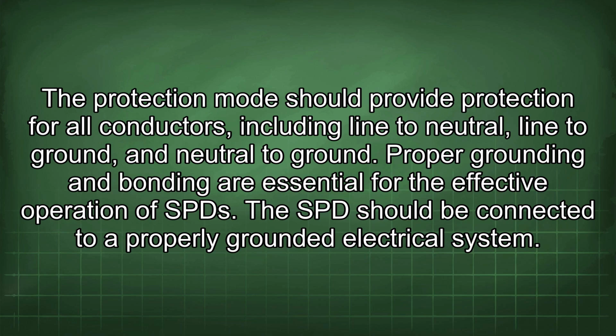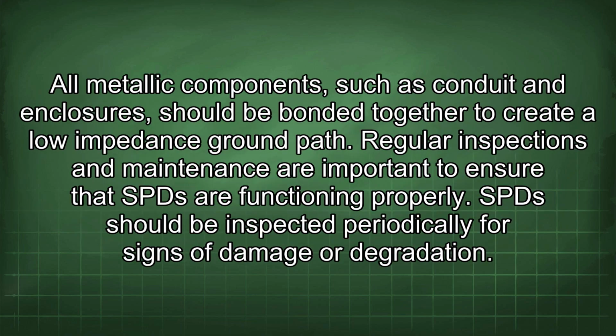Proper grounding and bonding are essential for the effective operation of SPDs. The SPD should be connected to a properly grounded electrical system. All metallic components, such as conduit and enclosures, should be bonded together to create a low-impedance ground path.